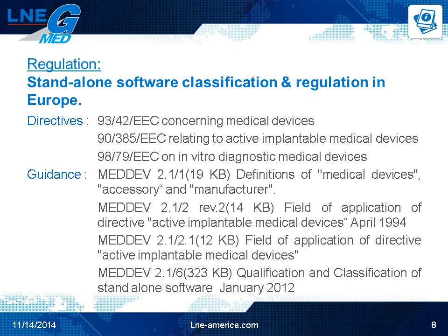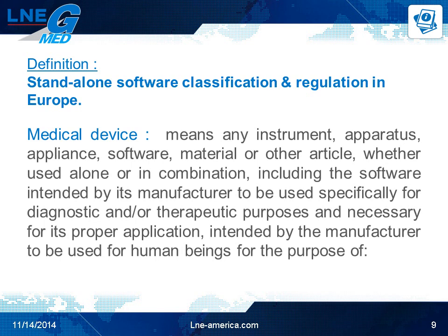MEDDEV 2.1-1 concerns the definition of medical devices, accessory, and manufacturer. MEDDEV 2.1-2 Rev2 talks about the field of application of the active implantable medical devices directive, and specifically gives important information regarding accessories of active implantable medical devices, because such accessories are considered to be active implantable medical devices. MEDDEV 2.1-2.1 also covers the active implantable medical devices directive. And finally, MEDDEV 2.1-6 talks about the qualification and classification of standalone software. Definitions are essential to ensure that the intended purpose of the software is consistent and in line with the applicable definition, so let's take a look at them.